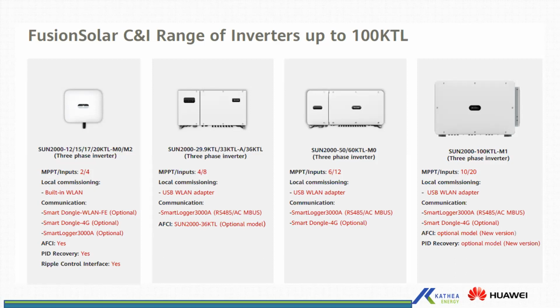And then our inverters have a ripple control interface, which uses 4 digital inputs. In such instances where you would need to control the active power of the inverter through an external device, sometimes it will be the municipality, like in the Cape Town region, they're introducing the SCADA system. Our inverters have a built-in ripple control interface for that. For the upper ranges, the smart logger is the one which is used for this ripple control interface.